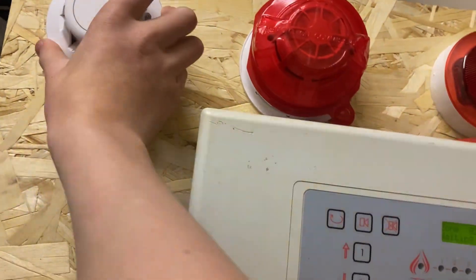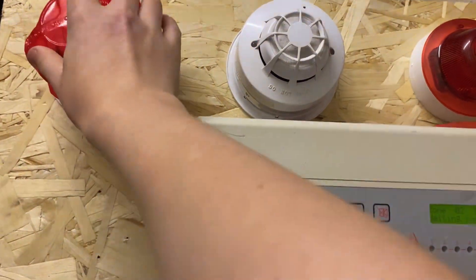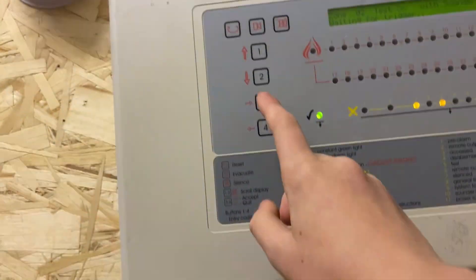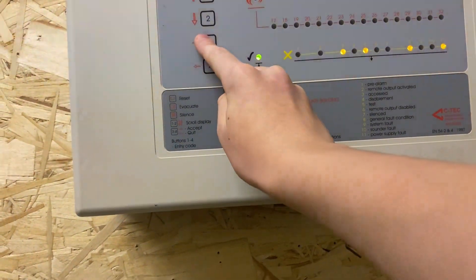Apollo — there we go. Brand new one, one of my 2018 standard ones. That can go on there. If that re-triggers, that is faulty. Zone three test on with sounders on.